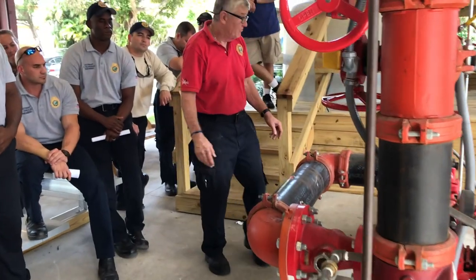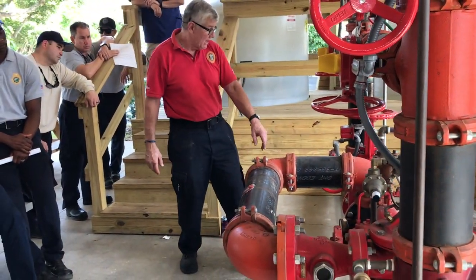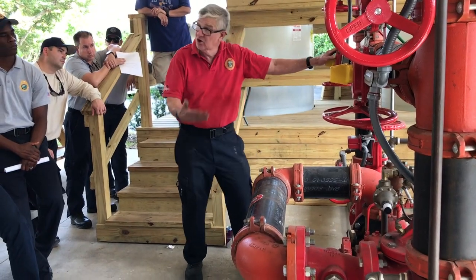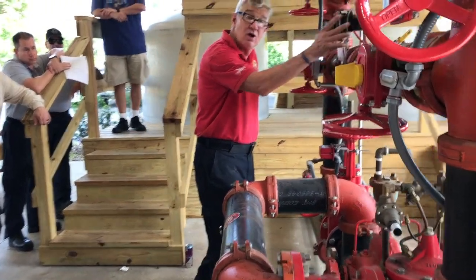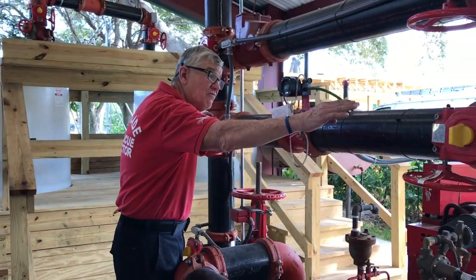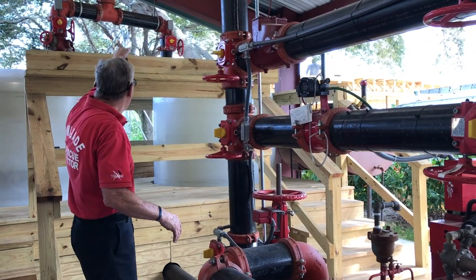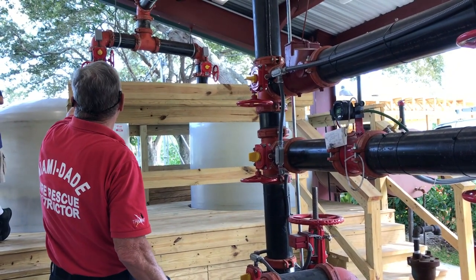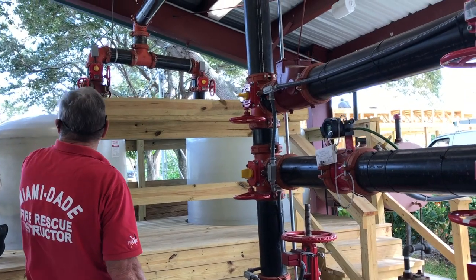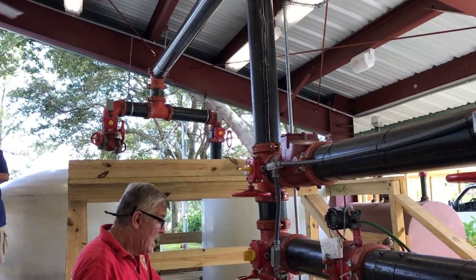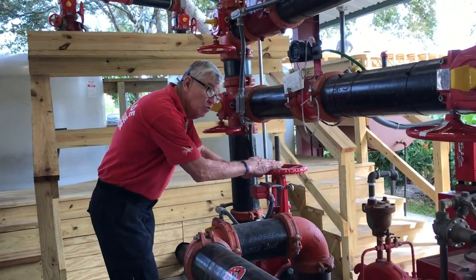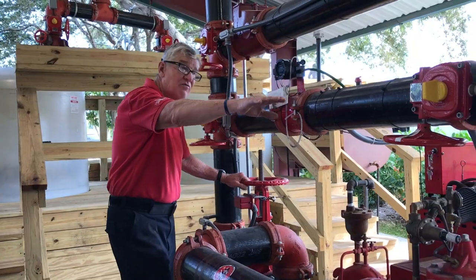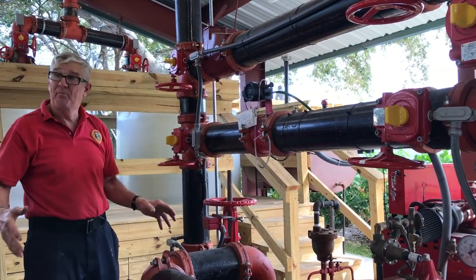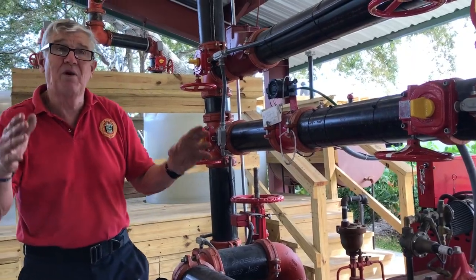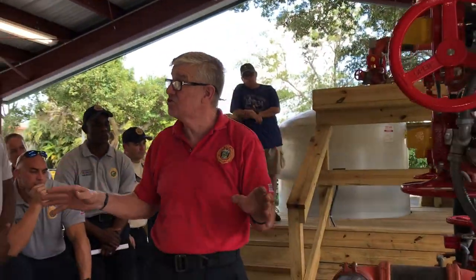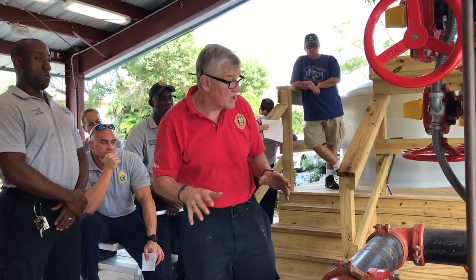You have your control valves. The way this is set up is you have a bypass, and in this particular installation, you actually have a flow meter. So we can flow water up through the check valve, through the flow meter, and it's piped back to the fire pump test header, test connection, back into those reservoir tanks. When we're working on the pump, we close the OS&Y's, we close the butterfly. In that case, we can remove the pump, and we would still be able to supply the system through the fire department connection. That's the beauty of the way that these are set up.